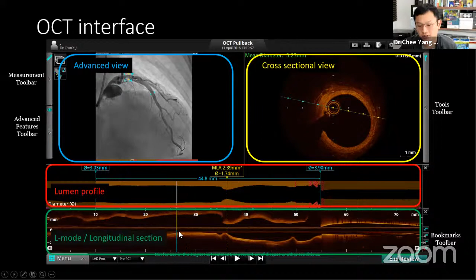In the top left, we have the advanced view panel. We can put our angio co-registration here, or we can also put our 3-dimensional reconstruction or 3-dimensional bifurcation assessments up here. Here's the lumen profile, which gives us the area of the lumen as computed by the software. In a longitudinal fashion, you can change it to the mean diameter as well. And this gives us a very quick assessment of where the stenoses along this vessel might be. And you can only get such a nice picture if your contrast clearance is good. That's why it's very important to have a good blood clearance when we perform OCT. Finally, down here, we have the L mode or longitudinal section. This is similar to what we have on IVUS.